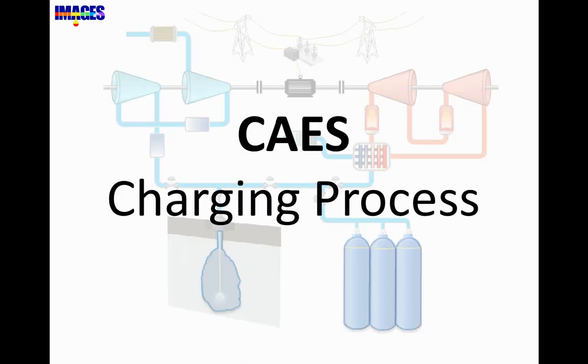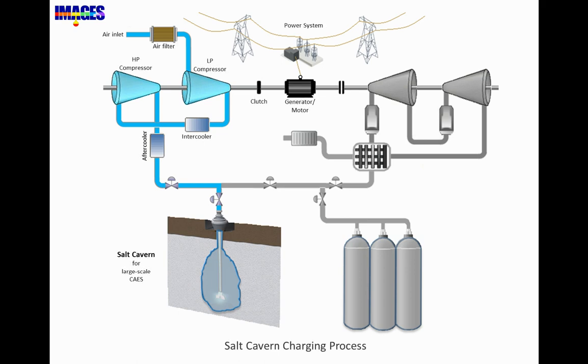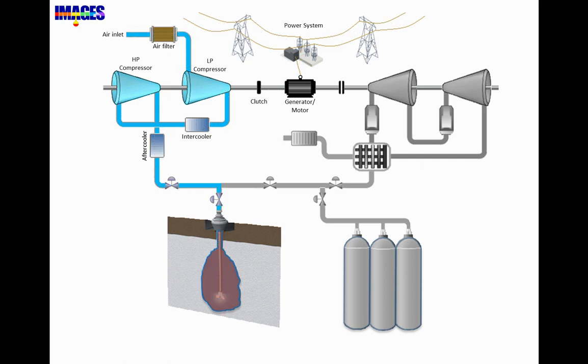First, let's take a look at the charging process. During the periods of low power demand, the surplus electricity drives a reversible motor-generator unit to run a chain of compressors for injecting air into a storage vessel. For large-scale systems, a high-capacity underground salt cavern is used. The energy is stored in the form of high-pressure air, with the pressure typically 40 to 80 bar.